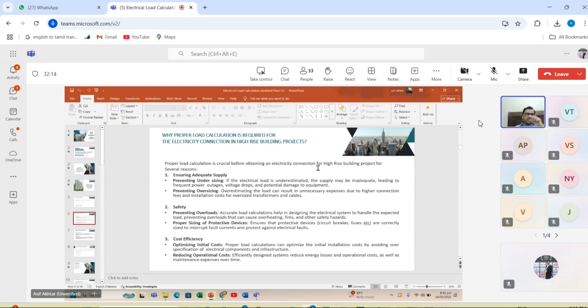So basically, it is very important to do proper load calculation before obtaining an electricity connection for a high-rise building project, for several reasons. Ensuring adequate supply, preventing undersizing. If the electrical load is underestimated, the supply may be inadequate, leading to frequent power outages, voltage loss, and potential damage to the equipment.